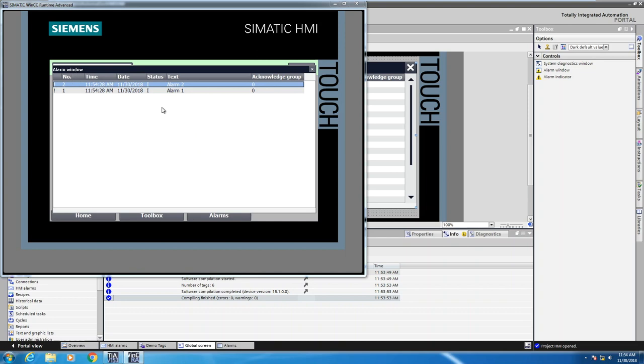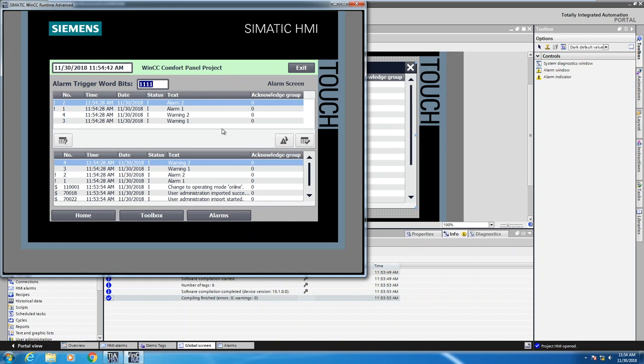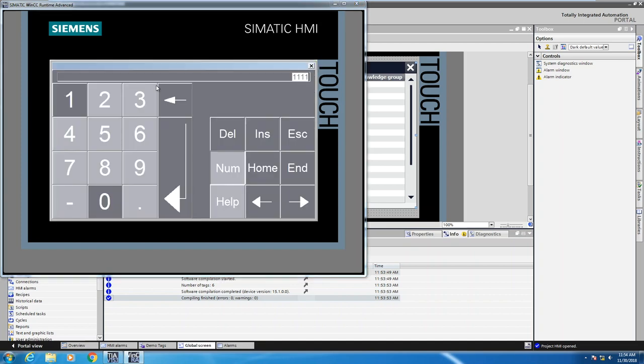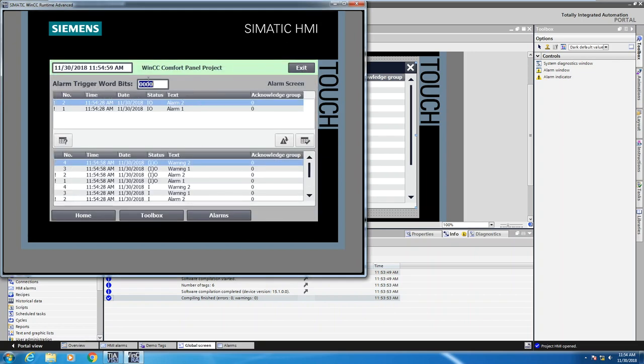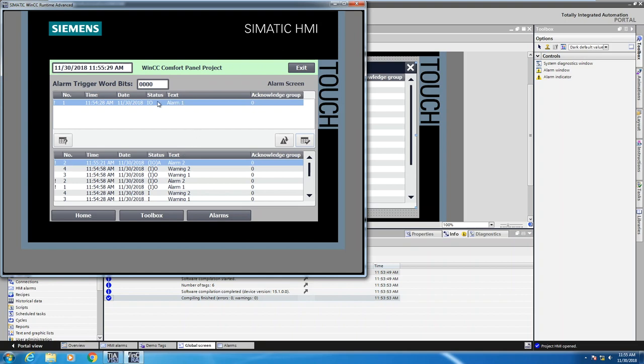The alarm window popped up and is being overlaid on top of my screen, displaying only my error conditions since warnings don't require acknowledgement. Looking at my alarm view, the first alarm view on the screen is showing all four alarm states as incoming states, and those states also show up in the buffer. Now I'll remove the alarm conditions by putting a zero in the IO field. My error conditions still show up in the alarm view because they have not been acknowledged, but down below in the alarm buffer we now have incoming and outgoing alarms — each alarm state is represented. If I select an alarm and press the acknowledge button, and that alarm condition is gone, it will remove that alarm from the alarm view. So we have incoming, outgoing, and acknowledged states — the A stands for acknowledged.